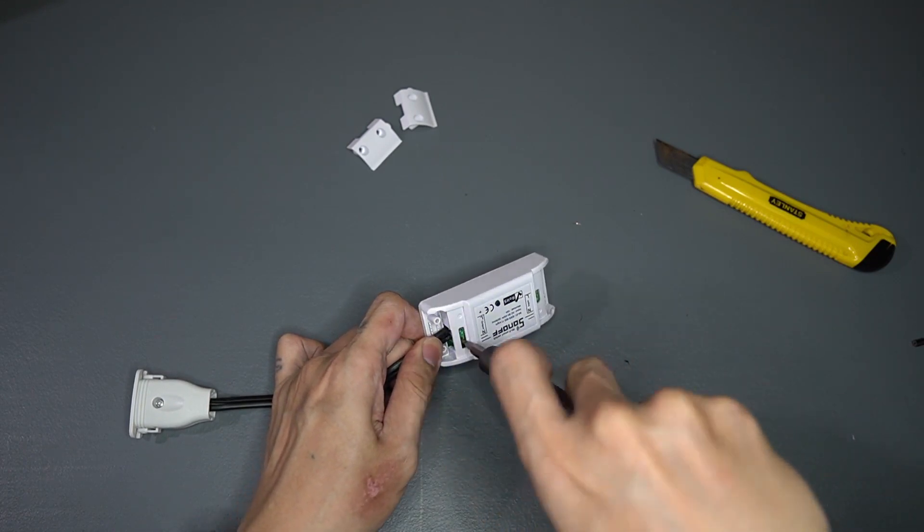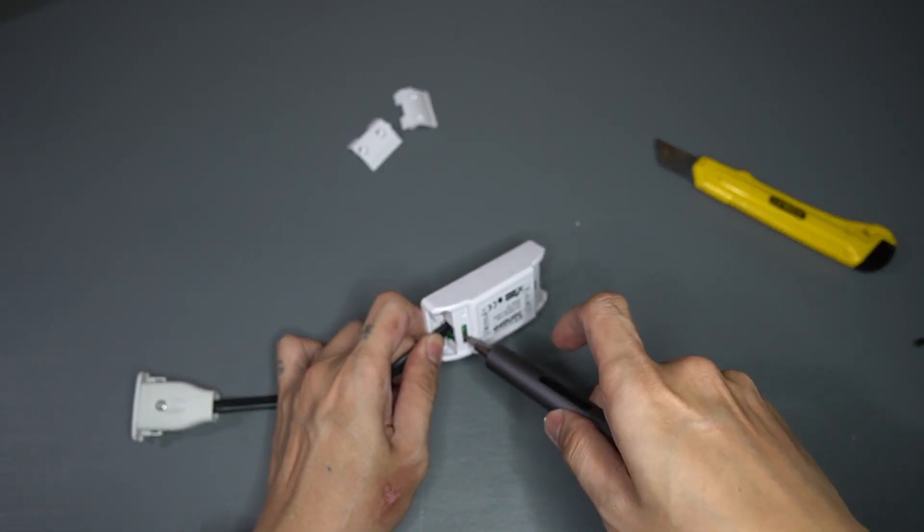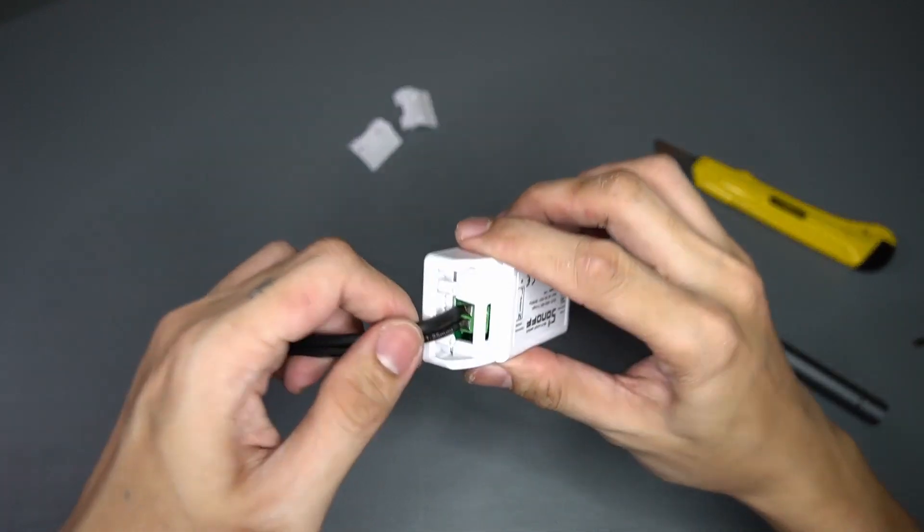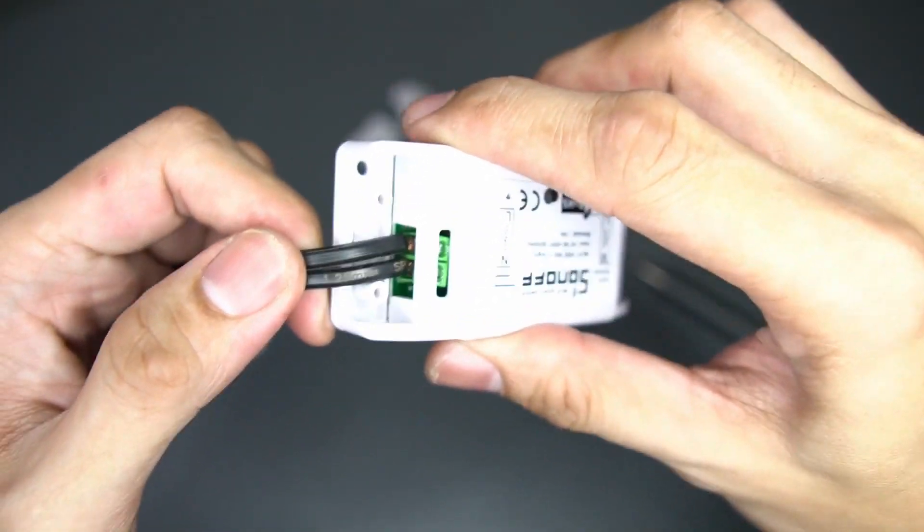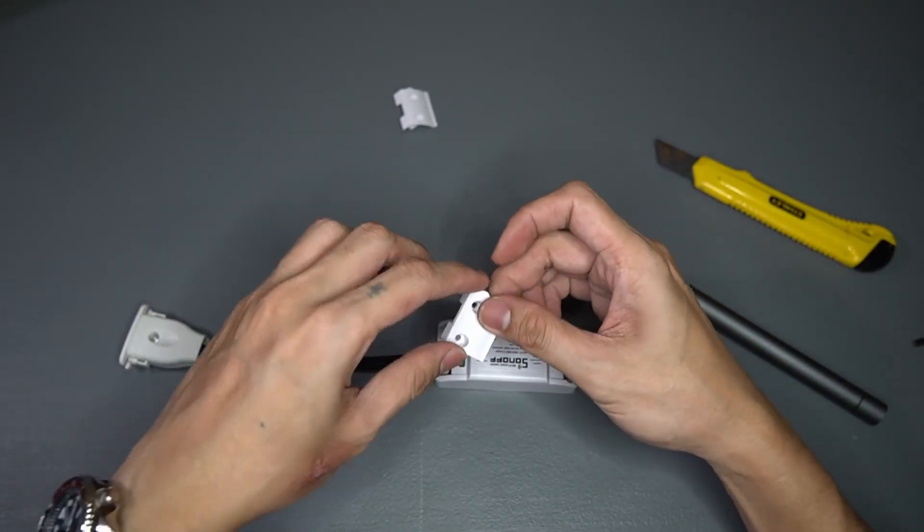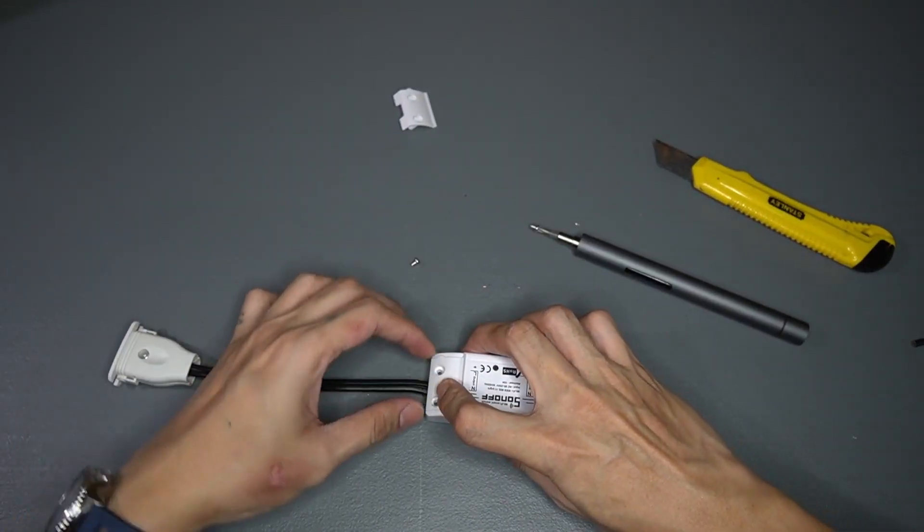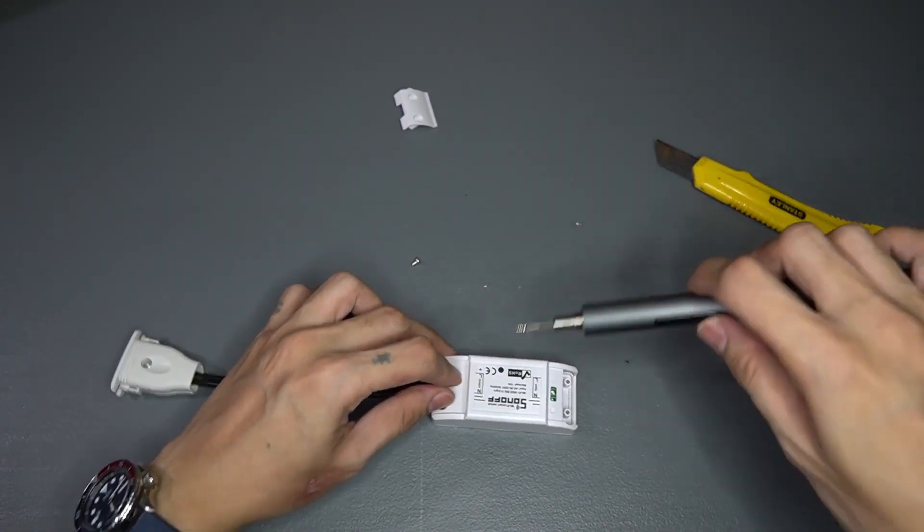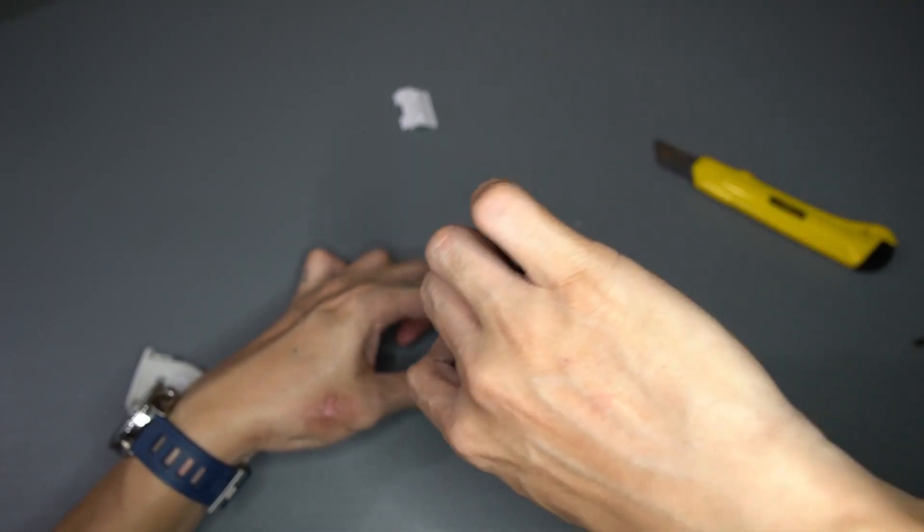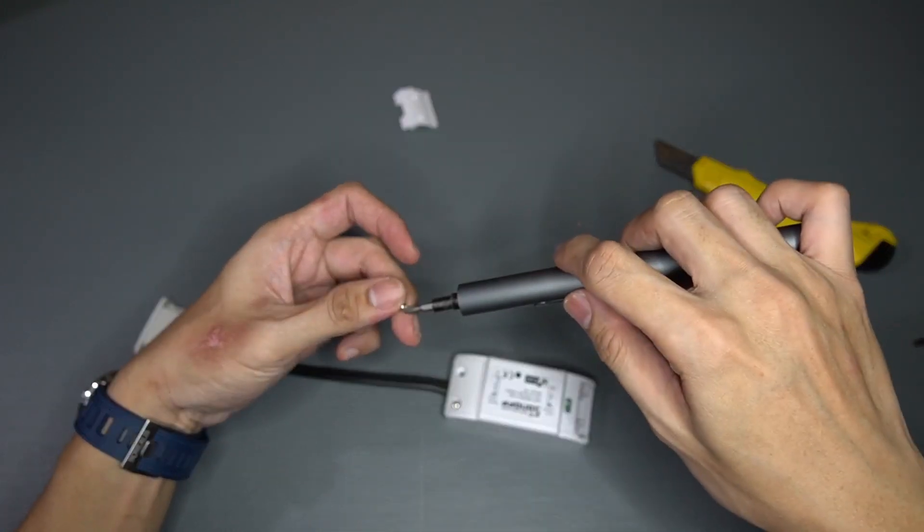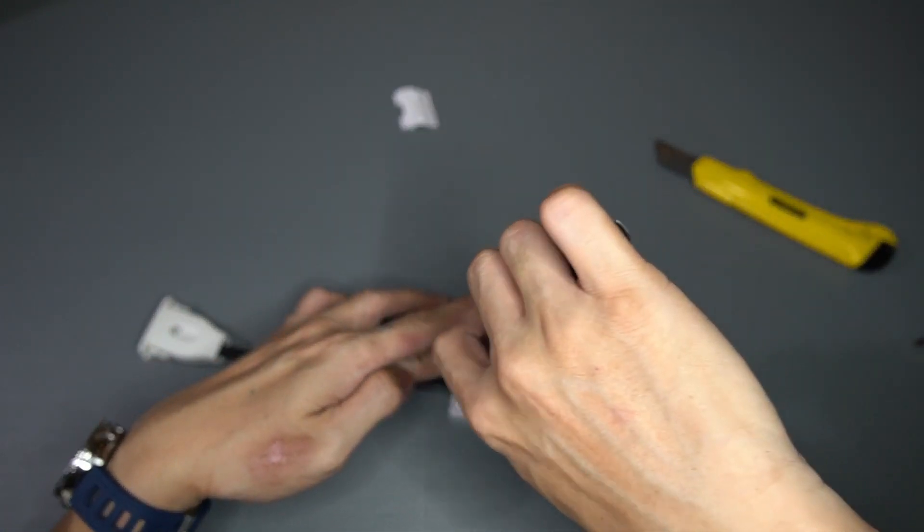Warning: make sure to check and double check your connections. No wire should cross the other terminal as this will cause a short circuit. Place the housing cover on top of the unit and fix it by using the provided screws as tight as you can, but not too tight. This cover clamps down the wire to ensure that it doesn't get pulled from the terminal.